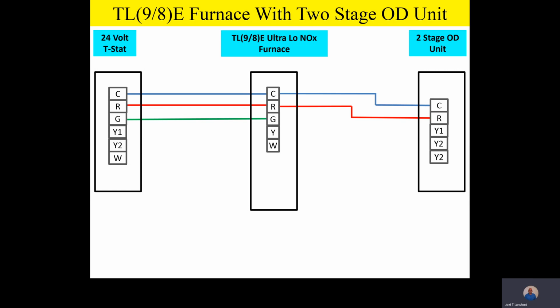the outdoor unit. So please note that when we set this up, we're going to have to select a speed tap on our cool terminal with a Y call on the furnace, and we're going to have to select a speed tap on the motor to give us 60 to 65% airflow on a Y1 call. And then when we select Y2, we'll show you some unique things that we have to do to wire this in order to have our Y2 output and our Y2 call from the outdoor unit back to the indoor unit. So it's very straightforward, but let's go ahead and look at this very simplified block diagram.